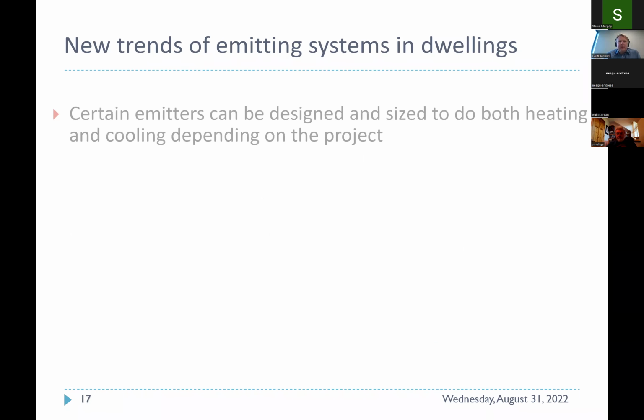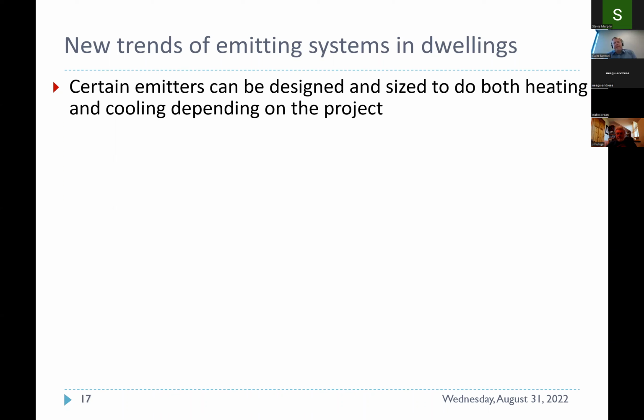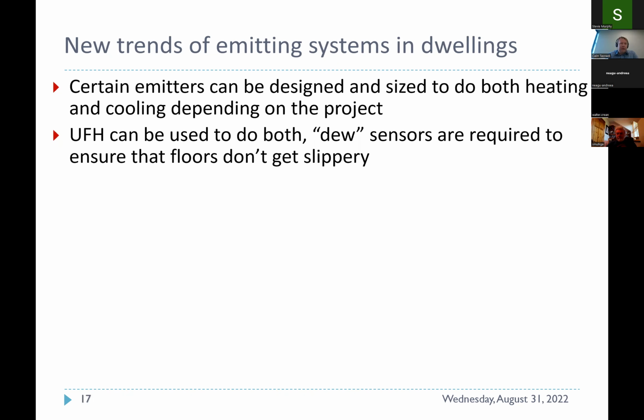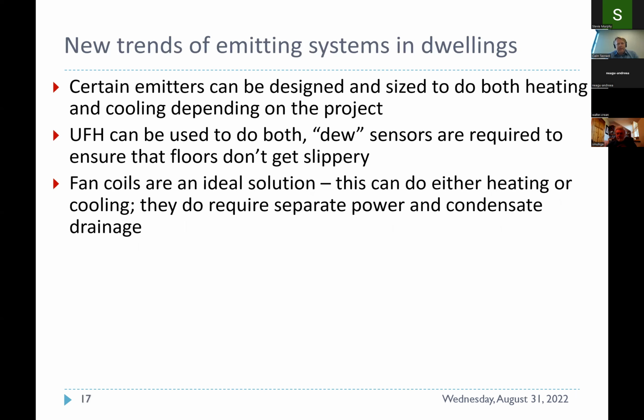We're looking at trends in the heat emitting systems in dwellings in particular. We have heat emitters that can do both heating and cooling, and you can actually use underfloor heating for that. We just have to keep in mind that, in particular for us here in Ireland, where we have high humidity, if we are pumping chilled water into the floor, we can have dew forming on it, so it can get slippery. For that reason, you require dew sensors, and then you have to limit the actual chilled water temperature that goes into an underfloor scenario.